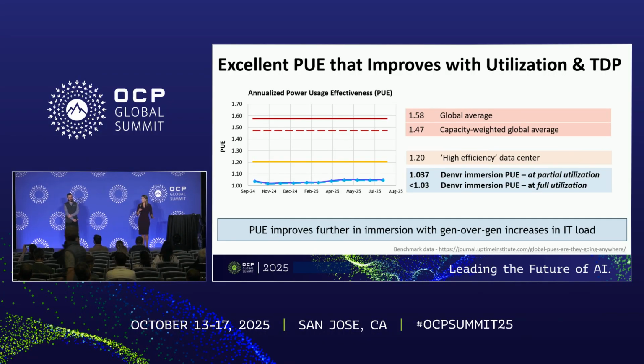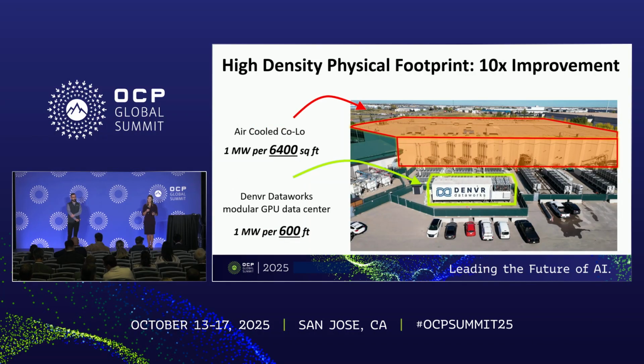The global average PUE is about 1.58. The Denvr Dataworks modular deployment is able to get below 1.04, and at full utilization and higher TDPs, which is where compute is moving in the future, we get below 1.03. This is a significant improvement for us, and it's really exciting from an operational perspective, and one of the key reasons why operating with immersion just makes sense.